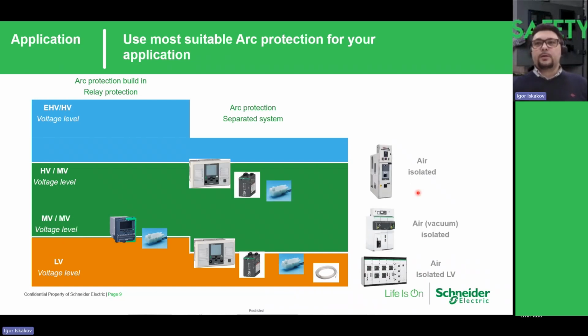When we speak about this air-insulated medium voltage switchgear, again, on the first level we suggest using the system, because it's a separate arc flash system. It's easier to understand, and in this case it does not need complicated engineering. Anyway, we can also use protection relays with built-in arc flash protection. This needs more complicated engineering and, in many cases, GOOSE communication and understanding the logic behind it. But the system is quite easier to understand and implement for medium voltage.